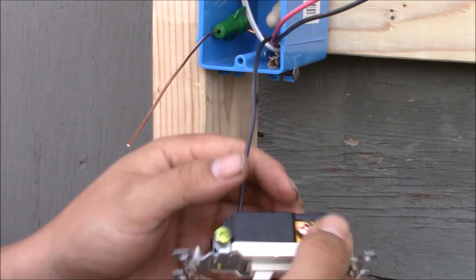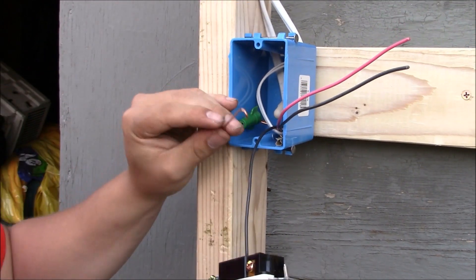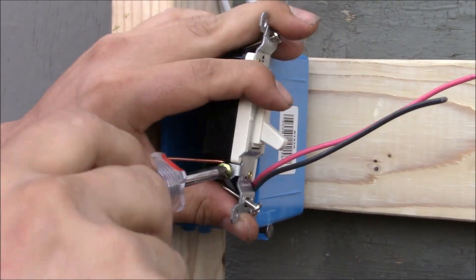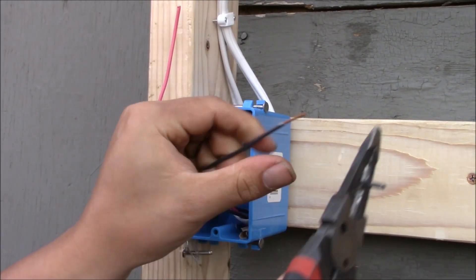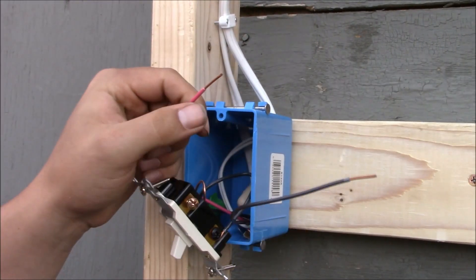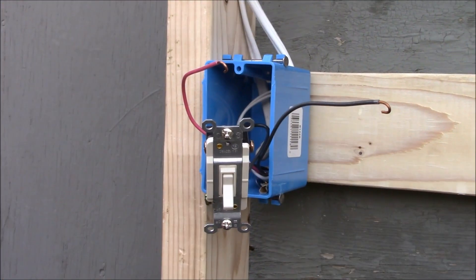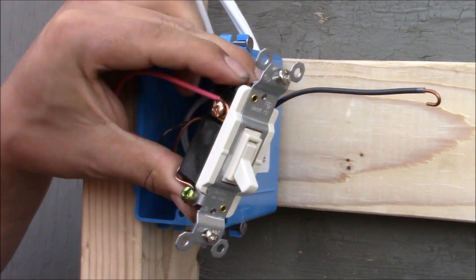Next, we're going to attach the ground wire to the green grounding terminal on the bottom of the three-way switch. We're going to put the two traveler wires to the brass terminals. It does not matter which one goes to which, but it's extremely important that the traveler wires only go to the brass terminals. Put one traveler wire to one brass terminal and tighten it down, and the other traveler wire to the other brass terminal.